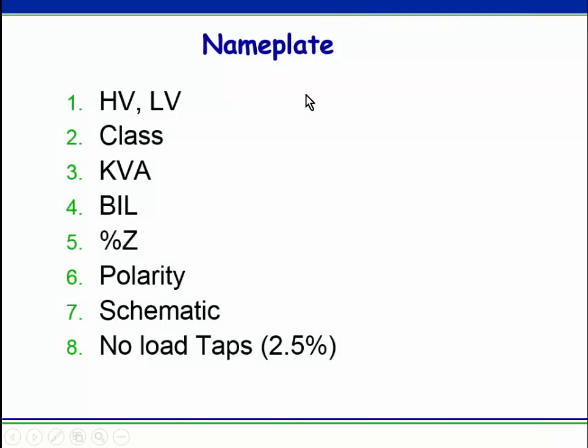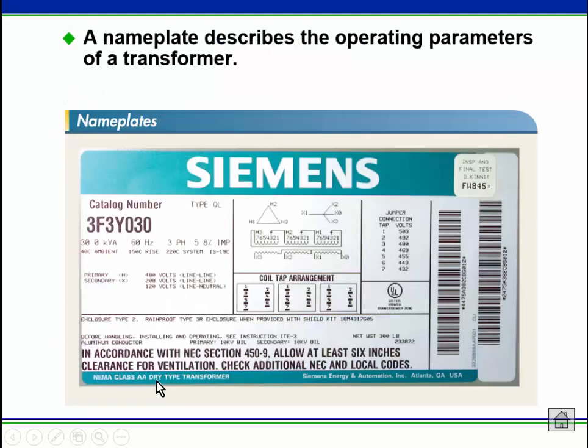Alright, some things you're going to see on the nameplate, and we're going to go through what some of these things mean. The voltages, kVA, BIL, some of these things. So let's take a look at some of these. Here's a nameplate. Notice the nameplate shows this one a delta Y configuration. Notice the primary leads are labeled H1, H2, H3, and the secondary leads X1, X2, X3. That's the normal convention. And X0 means it's grounded or it's a neutral point.